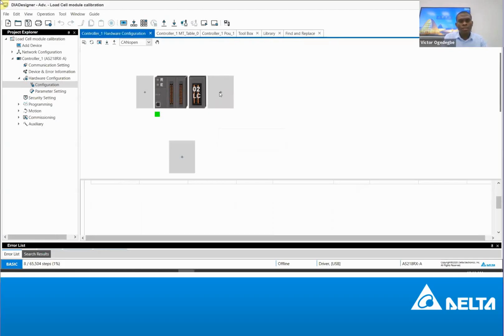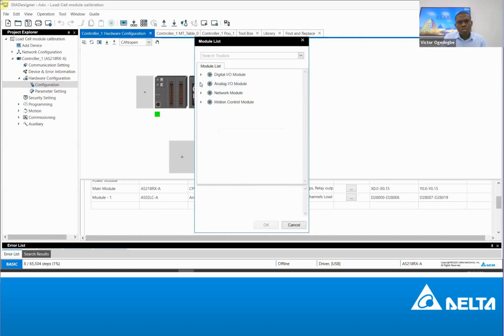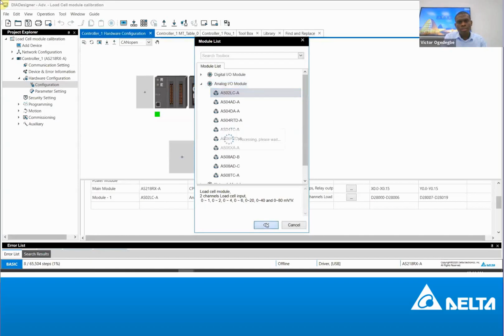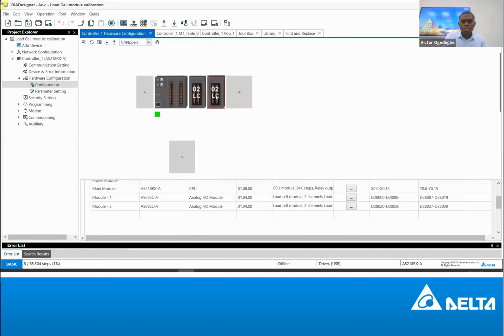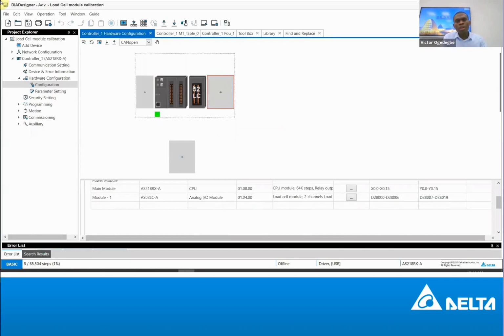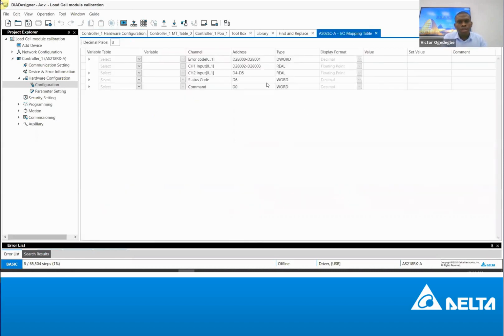There are two ways. Either you add it, if you double click, analog, load cell module is an analog. If you add it, you see it's added, but I don't need this, so let me delete it. Now I have my load cell module added. What I was saying is that if you click on the CPU, you see it already mapped some addresses to these load cell modules. If you click on this tab, you see detailed information of the address assigned to it.